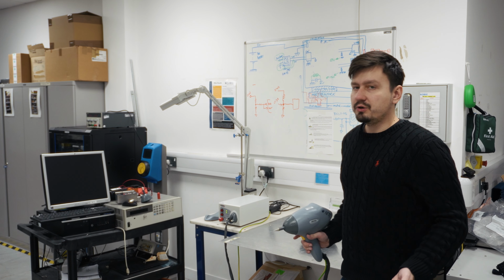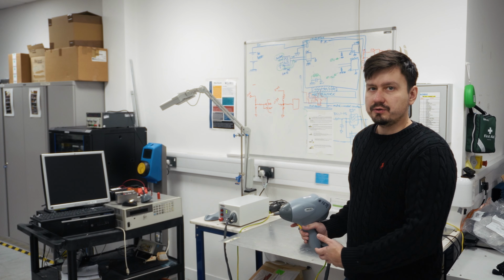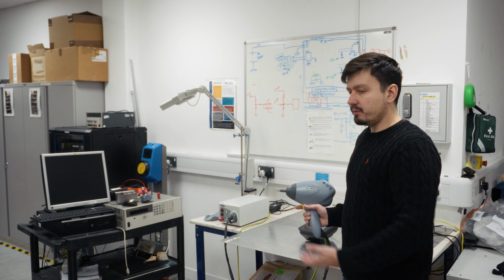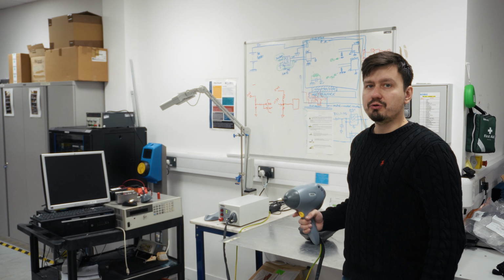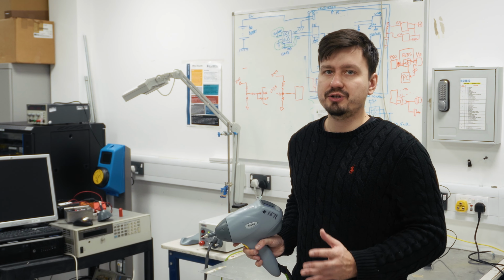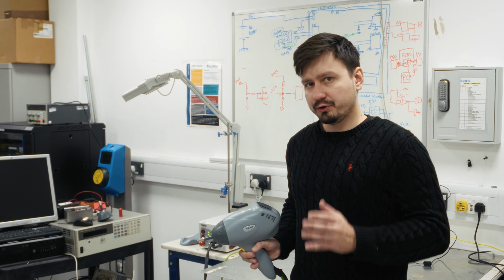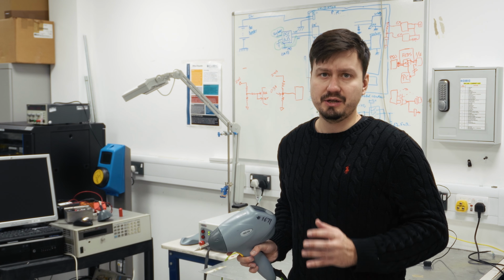We're not going to do air discharge into the coupling plane because it's metal, so you use contact discharge instead. Now that I've satisfied myself with discharging ESD into the coupling plane, I'm going to set my voltage back to 4 kV and do contact discharge on the DUT itself.